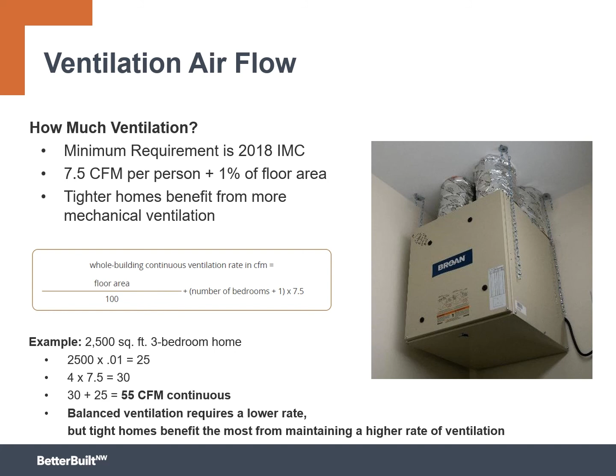These systems are supposed to be commissioned, meaning measurement and verification to show they're actually moving the air they're supposed to move. If you install equipment that doesn't work, you've spent money on something that doesn't deliver for your homeowner, which typically leads to moisture problems or poor referrals.